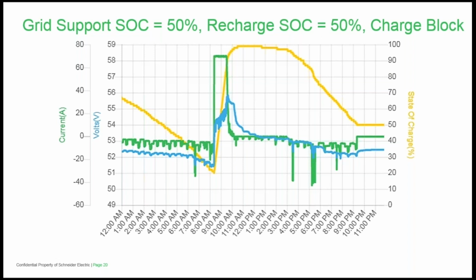The usefulness of state of charge cannot be underestimated. It allows depth of discharge to be very precise, contributing to maximize battery life. In fact, you could disable the charger and wait until DC coupled solar charges the battery to a desired state of charge. It doesn't need to be a full charge either. You could choose to export back to the main panel down to a particular state of charge during a specific block of time. These are screenshots of real power that I logged with my system.